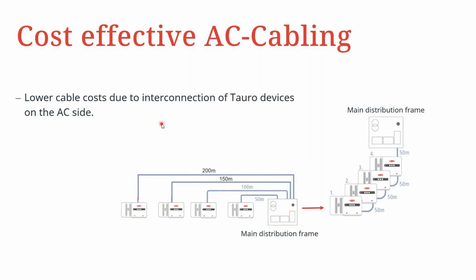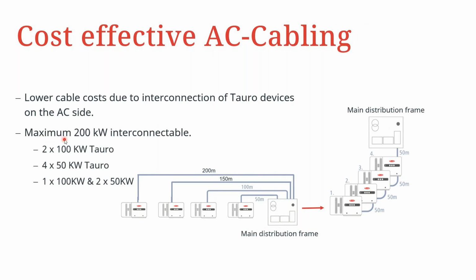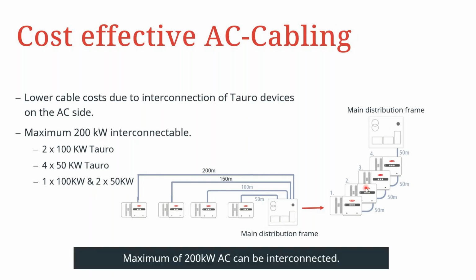This is made possible because of this special feature, the AC daisy chaining option of the Fronius Tauro. And this, of course, lowers cable cost due to the interconnection of Tauro devices on the AC side. It is possible to have a maximum of 200 kilowatts that are interconnectable. Okay, so this is basically a recommendation. You're not supposed to go beyond 200 kilowatts per interconnection, let's say. That means you can have 2 units of 100 kilowatts Tauro or 4 units of 50 kilowatts, as is represented in this case. Or you can have a unit of 100 kilowatts and 2 units of 50 kilowatts, depending on your system design regime. Good.